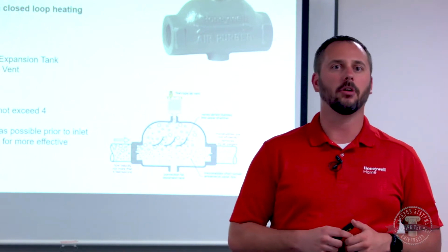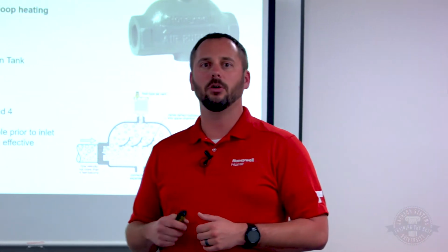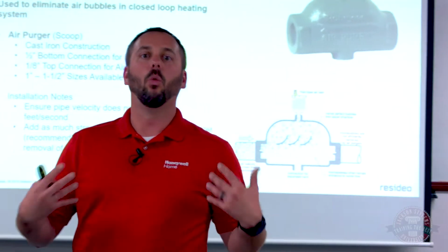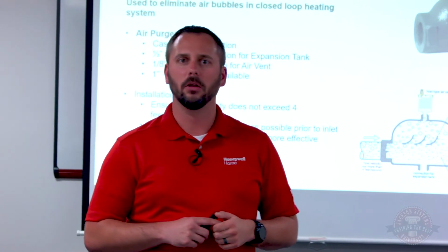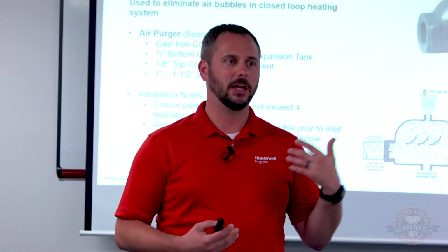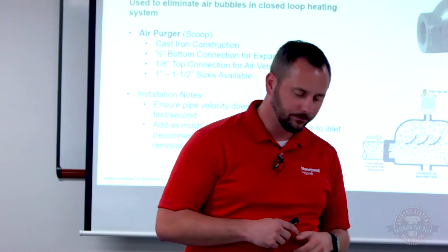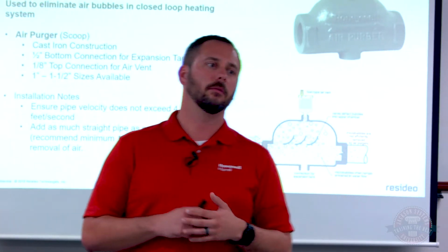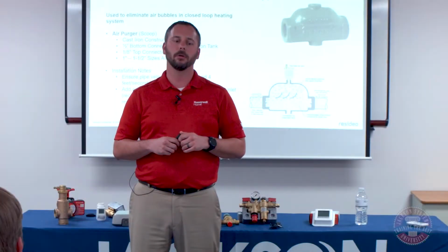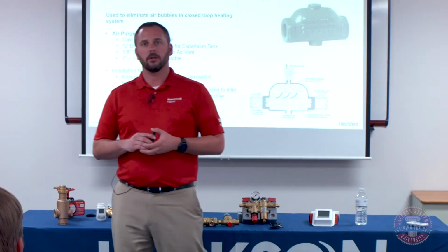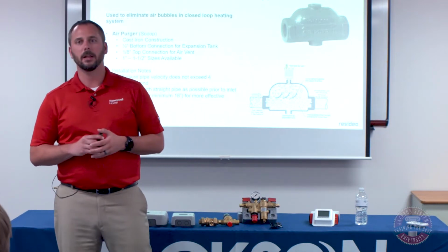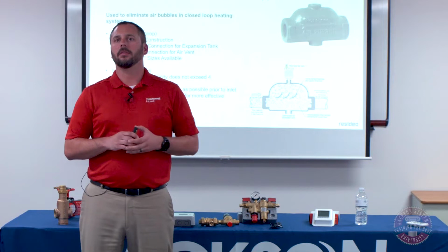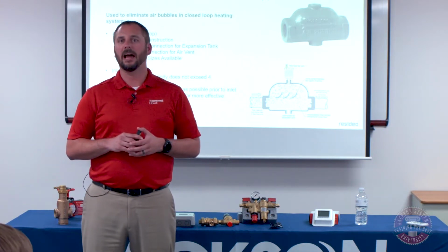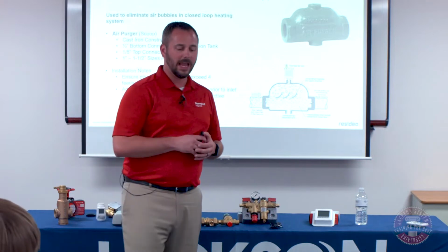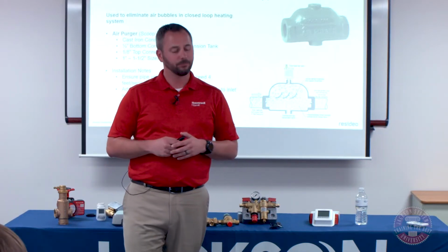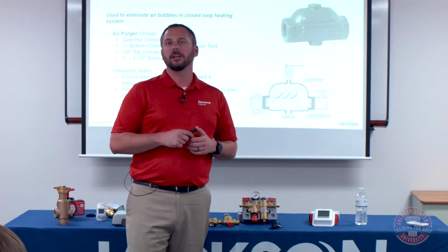So there are a couple of big drawbacks to this. First, it does not do an effective job of getting rid of the microbubbles. As the water starts to heat up, it really brings those small bubbles out. That's a lot of times where you hear the noise, the gurgling, the noisy pipes, from the microbubbles. This does a great job of collecting the big air bubbles, but not the microbubbles. You have to add a third-party air vent. A lot of the automatic air vents, and I'll talk about this in a minute as well, are not the best. They last a few years and then start to leak. So we have some high-capacity ones that are very long-lasting, but you have to add air vents to this, and the installation is kind of critical as well.